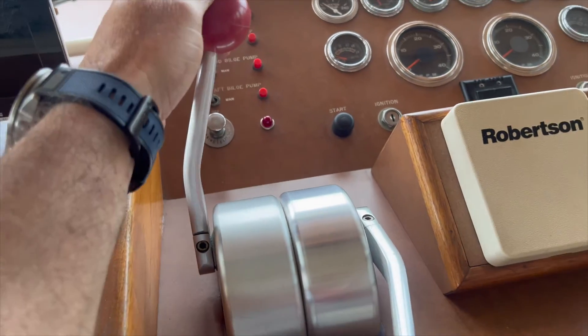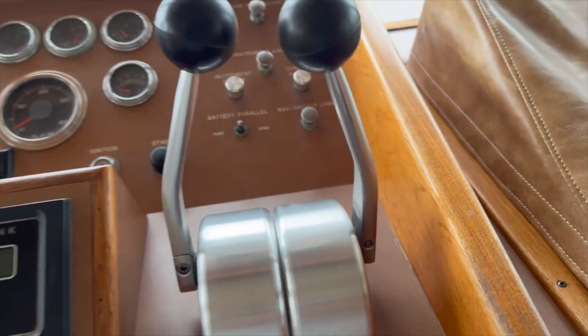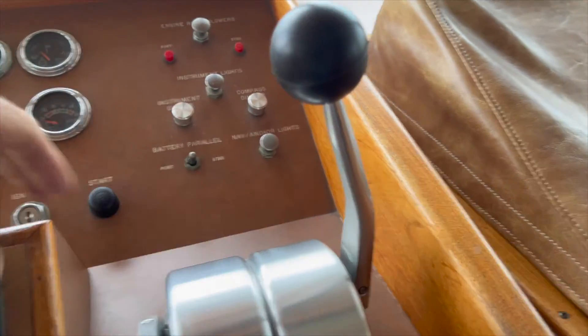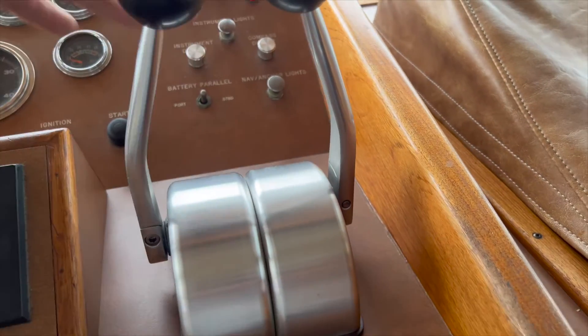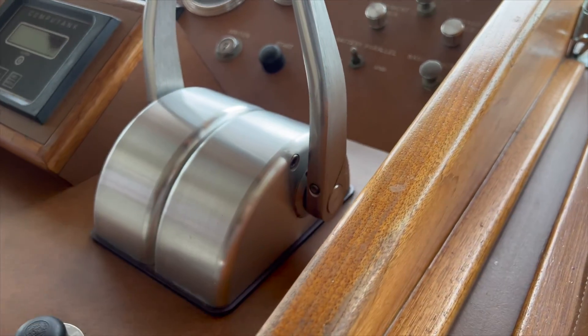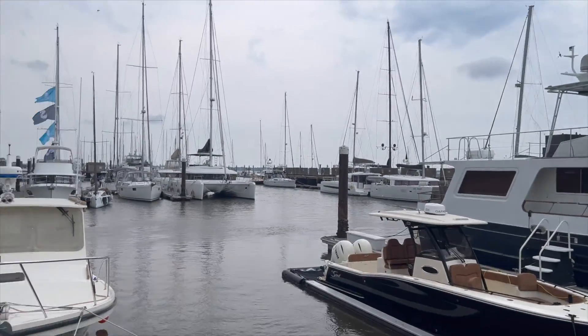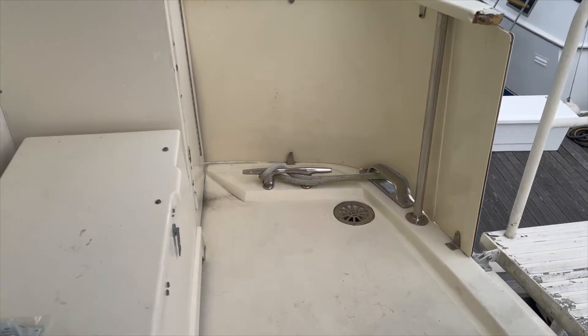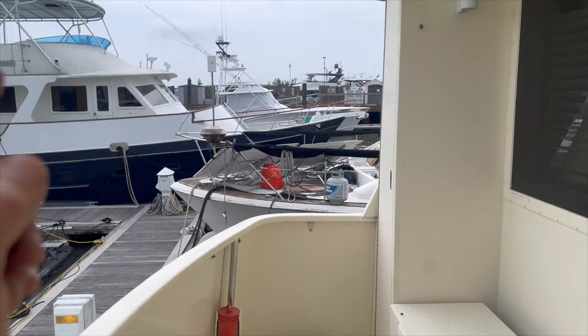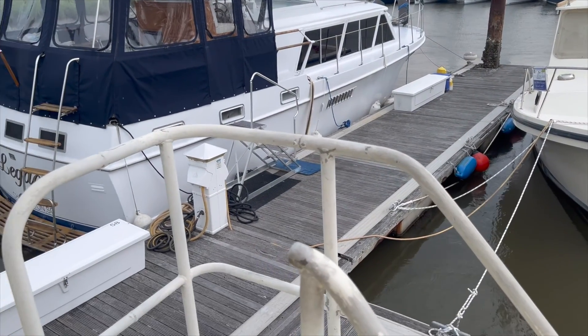Testing shows it's going all the way up and all the way back, but not forward — so I've got to bleed my own system too. There are bleeders right here — bled all those out, both downstairs and the mixing valves are good. We're good to go. There's a tornado watch coming, just fixed the bilge pump on Ship of Fools around the corner. Thanks for watching.